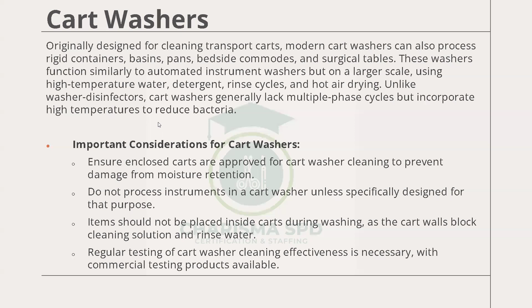Debris should be removed from the washer traps daily. When you open and look in there, at times there are instruments that have fallen in. You take them out. If there is debris, take it out before it blocks the drains. So always pay attention to that. On our side, we have an instrument like the Baja drill. It has tiny, tiny instrument parts, and you have to be very careful with them or they will fall off into the washer. Sometimes when we go at the end, we pull everything out and pick some of those instruments from there. By the time you go to the other side, they are already waiting on those instruments. So you clean them, take those ones, and help them complete those instrument sets.